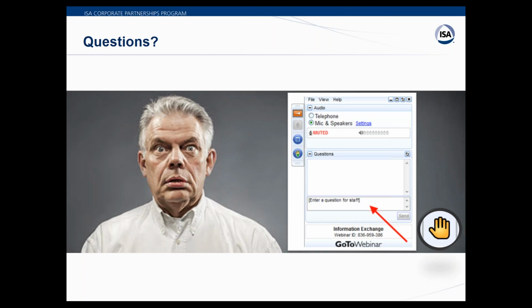But Roy said he wanted to do an up-down test on his pressure transmitter, and that's kind of just common practice. But really, if that make and model, and he does enough up-down tests, let's say he does 50 up-down tests, and he never observes hysteresis, you could save time by not doing an up-down test. But agreed, you should prove that to yourself, or prove that to your quality people before you make that decision.